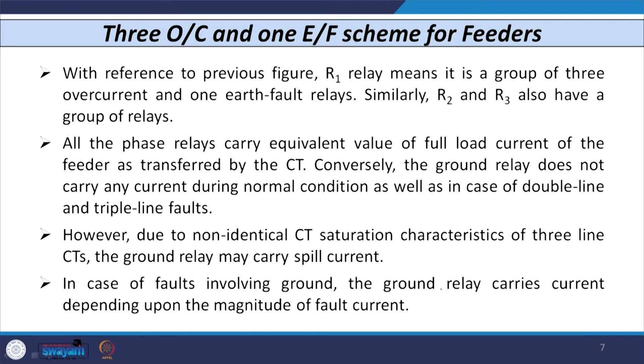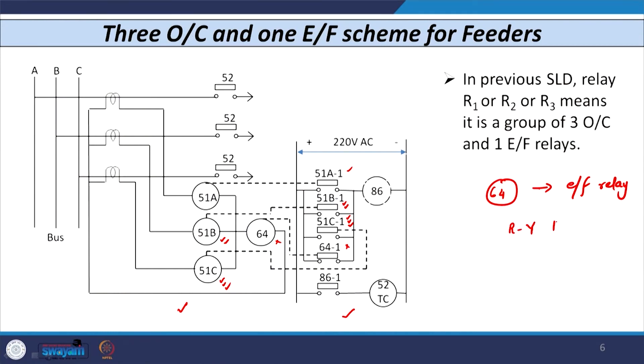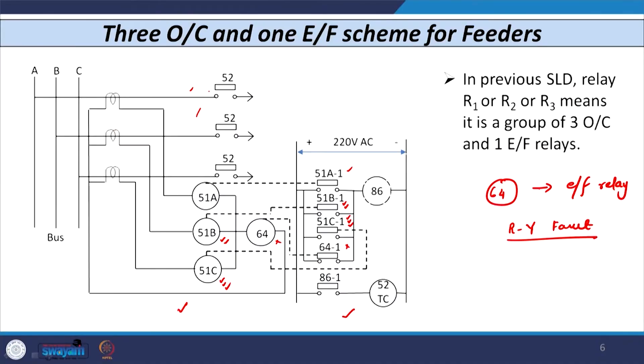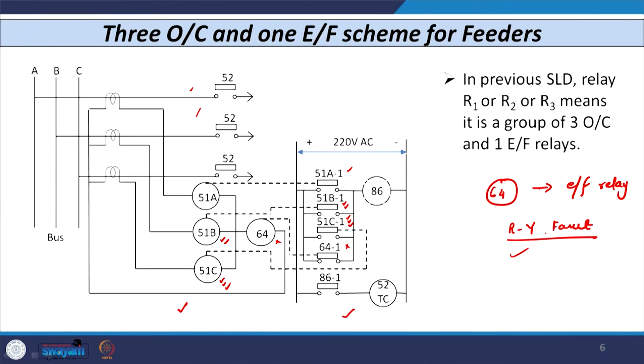When a phase fault such as R-Y fault (line-to-line fault) occurs, the phase relay must operate and the ground relay should not operate. The current in R and Y phases increases; in the secondary, units 51A and 51B are energized and their contacts 51A1 and 51B1 close, energizing the auxiliary relay coil 86, whose contact 861 trips and energizes the trip coil 52TC. For an R-Y-B triple line fault, units 51A, 51B, and 51C all energize and their contacts all close, initiating tripping.